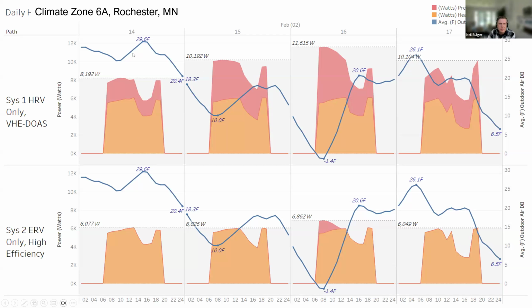This is a pretty cold week, always below 30 degrees. For the HRV, the model conservatively assumed electric heat turns on below 32 degrees, and you can see it almost doubles the peak demand in some instances. For the system doing some moisture removal, we could drop that threshold to 20 degrees, and the spike is almost half—about 6.8 kilowatts compared to 11.6. So it's a conservative estimate, and not all systems control frost this way.